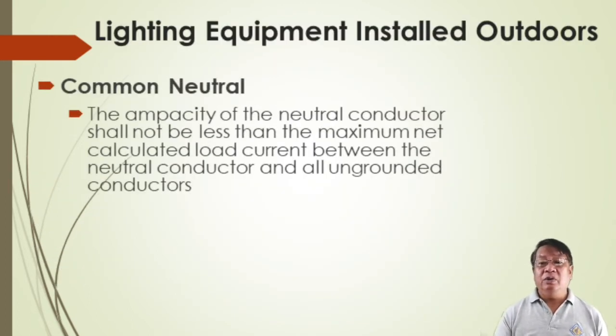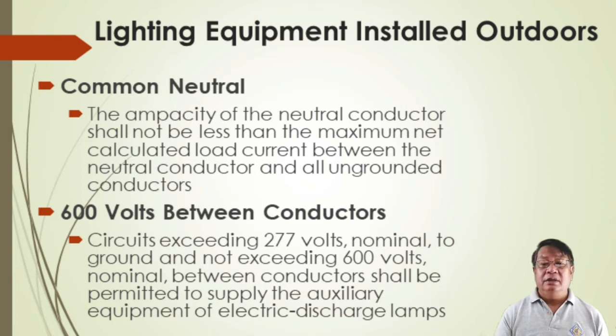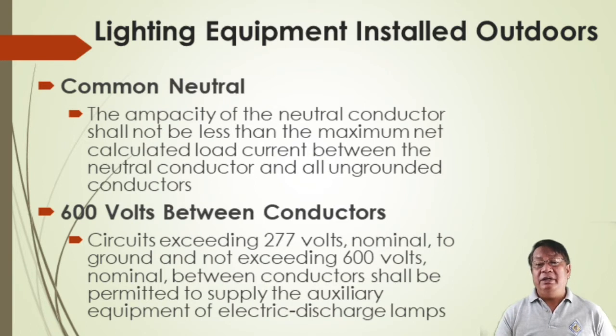For lighting equipment installed outdoors, the ampacity of the neutral conductor shall not be less than the maximum net calculated load current. For circuits exceeding 277 volts nominal to ground but not exceeding 600 volts nominal between conductors, it shall be permitted to supply the auxiliary equipment of electric discharge lamps.